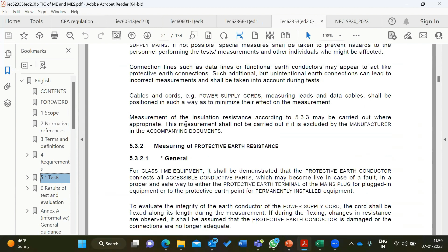I am just showing some of the requirements. For example, the first test, of course, is visual verification, the actual test. For example, clause number 5.3.1 measurements, 5.3.2, the first measurement is measuring of protective earth resistance, the most important subject for a class 1 medical equipment. Class 1 medical equipment has a metal body, which can experience a voltage which can be fatal. I will just read out for your information: for class 1 medical equipment, it shall be demonstrated that the protective earth conductor connects all accessible conductive parts. Very simple to understand. There is an earth terminal on the equipment, and this earth terminal must be connected to all exposed conductive parts of that particular machine. That means the body or different kinds of exposed parts.